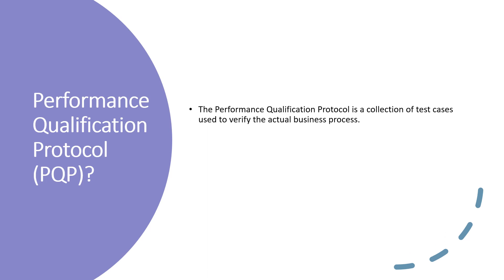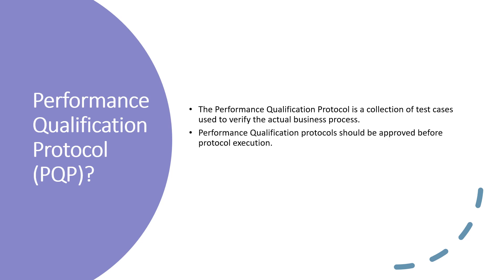Next, we will discuss what is a performance qualification protocol. The performance qualification protocol is a collection of test cases used to verify the actual business processes — for example, how to create the instrument method, how to create the processing method, and how to create a sequence in a chromatographic system. The performance qualification protocol should be approved before protocol execution — approved by the quality — then only the test can be performed.